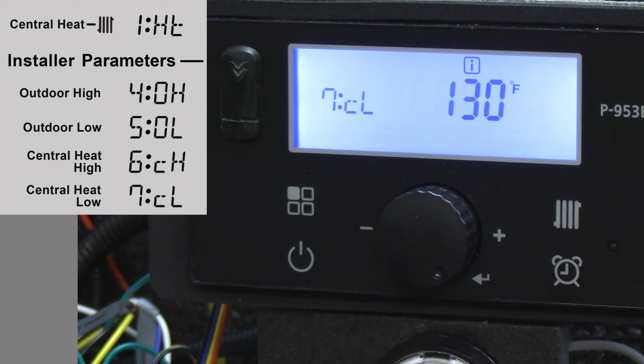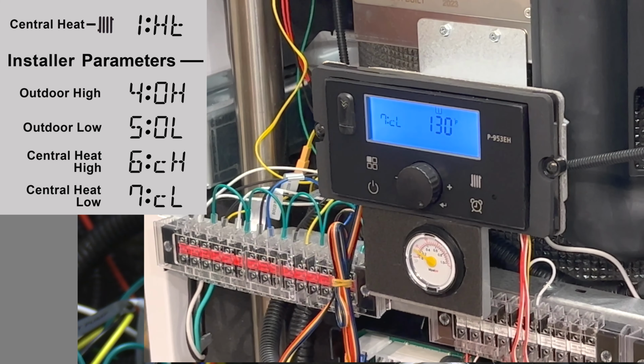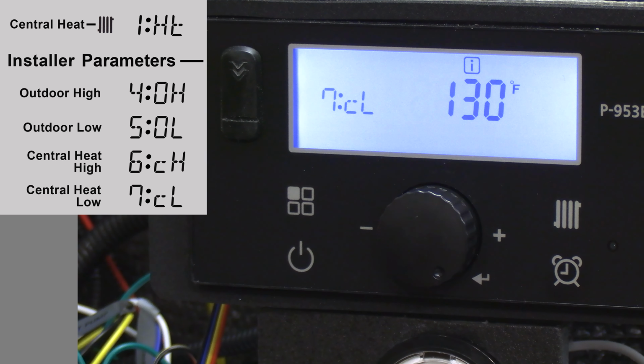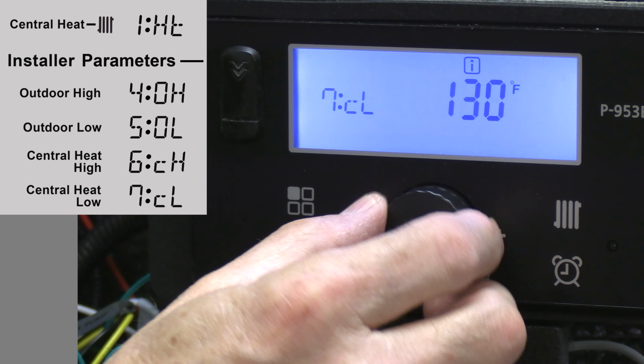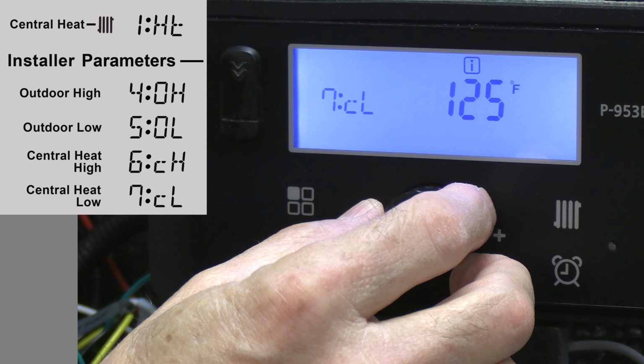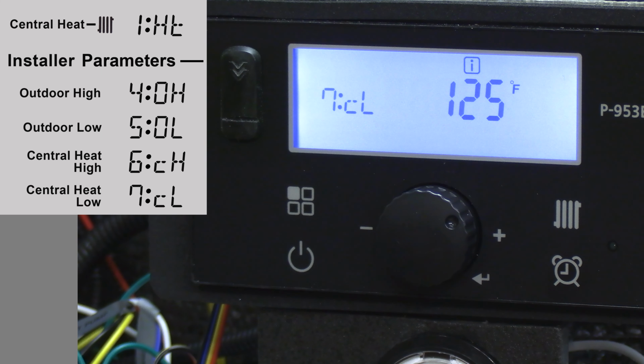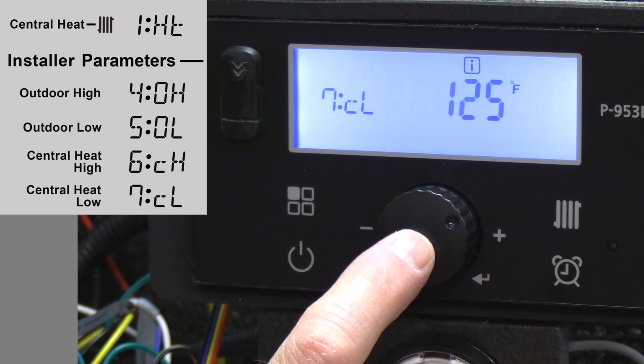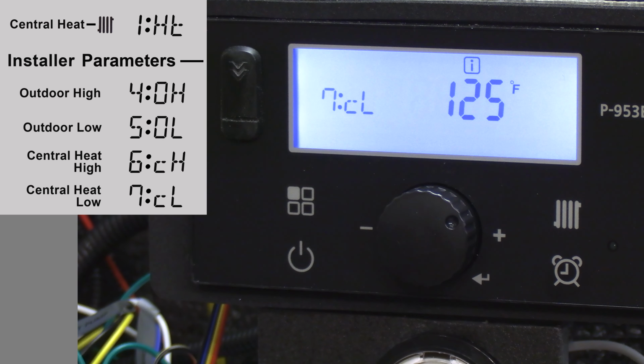Next is my low temperature. That's my central heat low. So an example of that is at 55 degrees or above, what is the minimum temperature I want to supply to that building? So that's based on your convectors. For example, slant fin baseboard might say 130, or maybe you want to drop that down to 120. And in this example, I'll say at 55 degrees, I only need 125 degree supply temperature. And I'm going to store that as well.